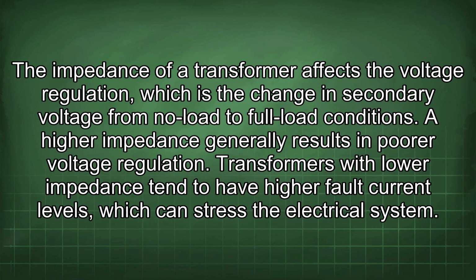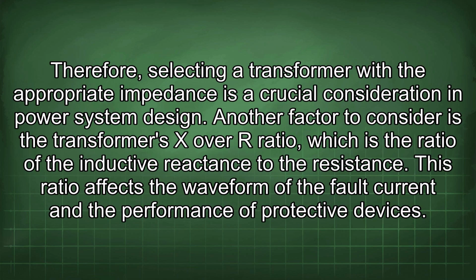The impedance of a transformer affects the voltage regulation, which is the change in secondary voltage from no load to full load conditions. A higher impedance generally results in poor voltage regulation. Transformers with lower impedance tend to have higher fault current levels, which can stress the electrical system. Therefore, selecting a transformer with the appropriate impedance is a crucial consideration in power system design.